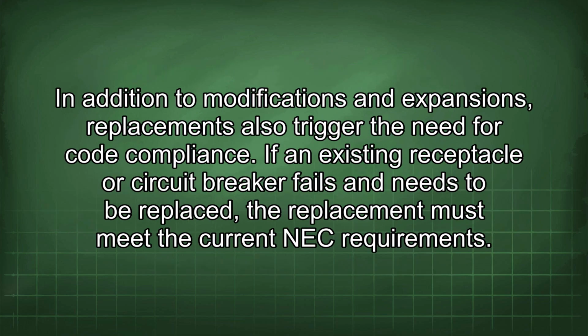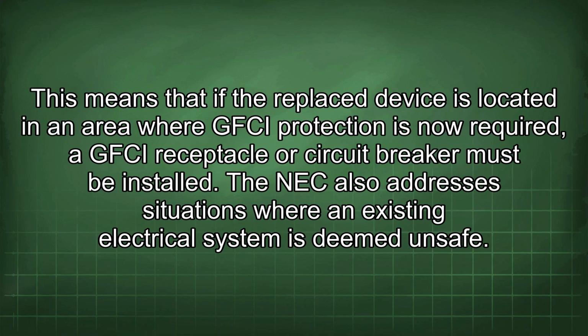In addition to modifications and expansions, replacements also trigger the need for code compliance. If an existing receptacle or circuit breaker fails and needs to be replaced, the replacement must meet the current NEC requirements. This means that if the replaced device is located in an area where GFCI protection is now required, a GFCI receptacle or circuit breaker must be installed.